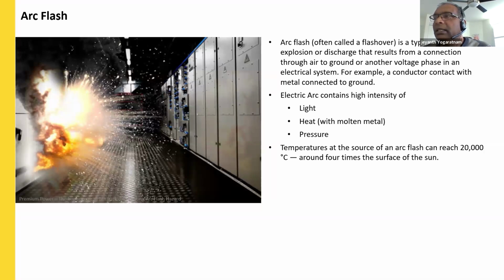Now the question comes, what is incident energy? Incident energy is the quantity used to measure the strength of the arc flash. It is calculated based on the bolted fault current at the source, the time taken to clear that fault, and the distance from the source. Those are the three parameters used in the calculation of incident energy. If you are interested in finding the exact equation, I can give you two references. One is the NFPA 70 standard document, the National Fire Protection Association standard. You may also refer to the IEEE 1584 standard, which gives all the equations at different voltages and how to calculate the incident energy, arc flash boundary, etc.